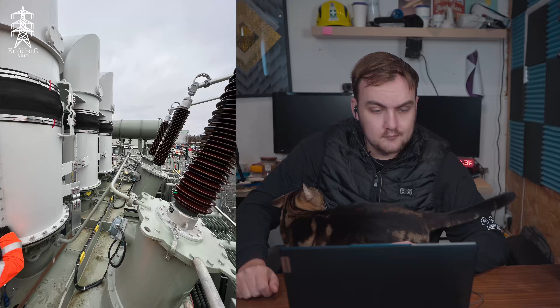And I've only ever worked on one substation which had a bus duct. It was a brand new substation we built in Wales. I'll post a picture up on the screen now so you can have a look at that. On the left of the picture is the bus duct, and on the right is a normal air insulated bushing, because the right side went off to the small switchgear yard, circuit breaker, VTs, CTs, that sort of thing, and then down into a cable, and that was the distribution network, and on the left was the higher voltage, in this case bus duct for a synchronous condenser.